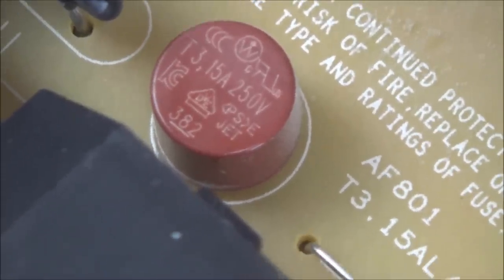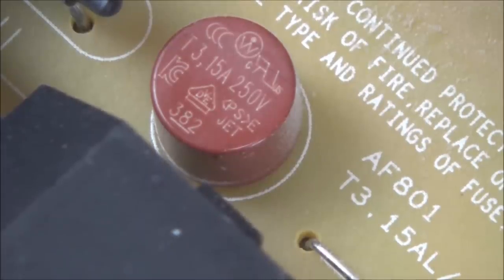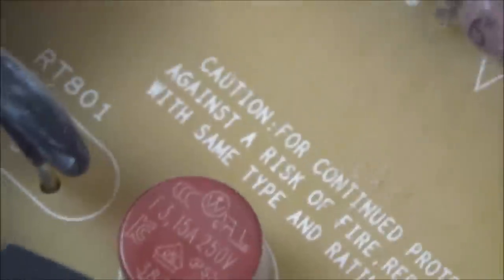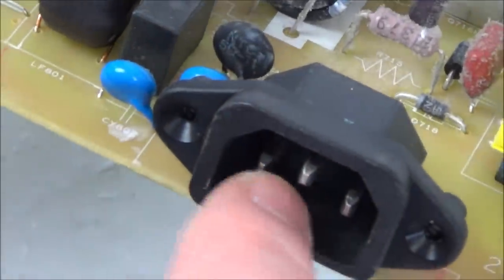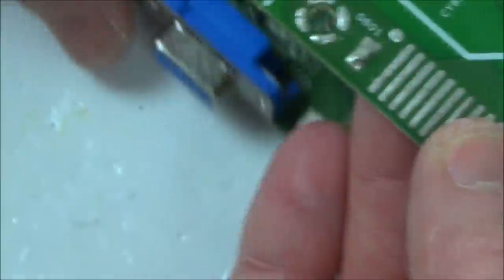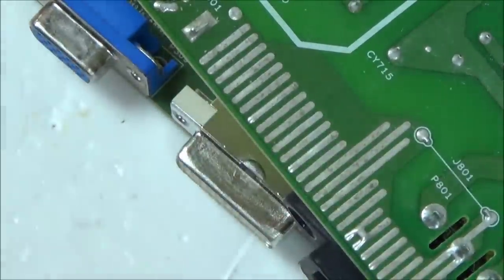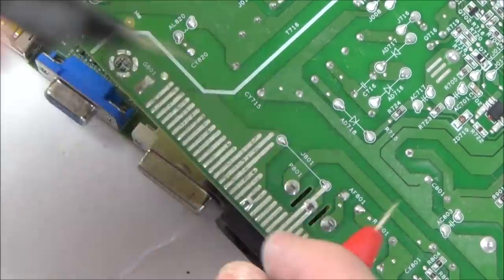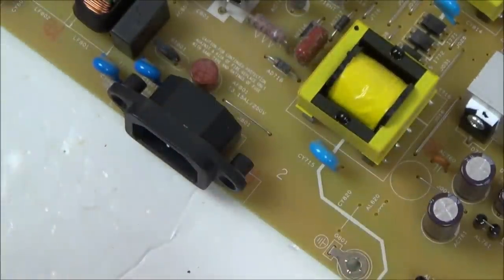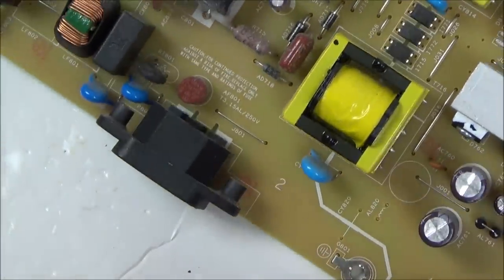Look at this - T3.15 amp 250 volts. I'm sure that's a fuse, and it does say: caution, for continued protection against the risk of fire replace only with same type and ratings of fuse. The top one's going to be the earth, and then we've got the two bottom ones - one of them goes straight up to that side of the fuse. I wonder if the fuse is blown. Let's just do a quick continuity test to see if we've got anything across that fuse.